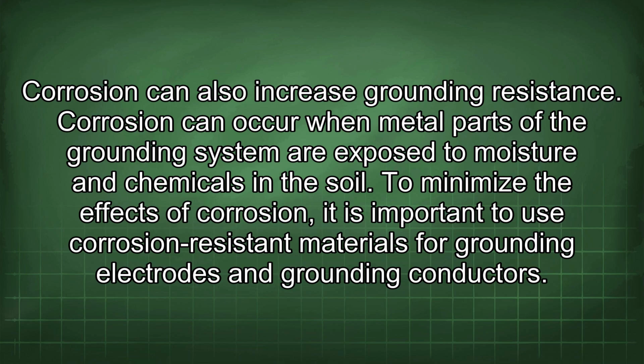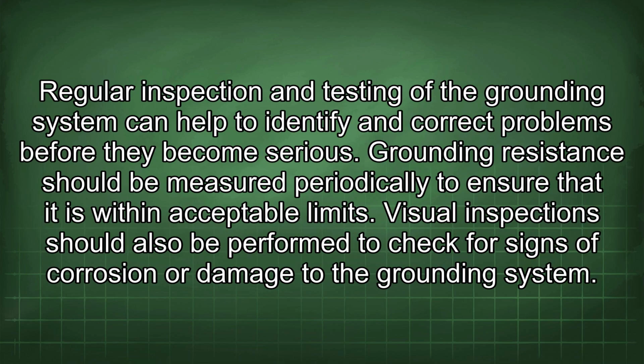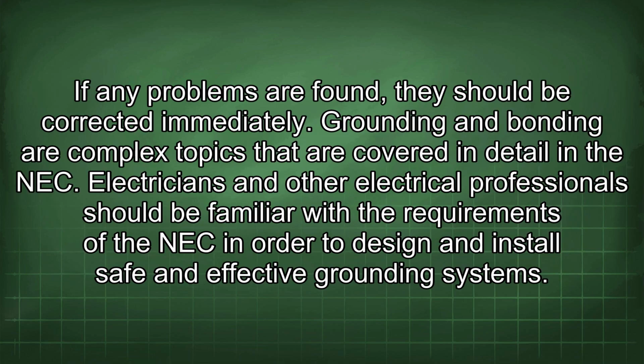To minimize the effects of corrosion, it is important to use corrosion-resistant materials for grounding electrodes and grounding conductors. Regular inspection and testing of the grounding system can help to identify and correct problems before they become serious. Grounding resistance should be measured periodically to ensure that it is within acceptable limits. Visual inspections should also be performed to check for signs of corrosion or damage to the grounding system. If any problems are found, they should be corrected immediately.